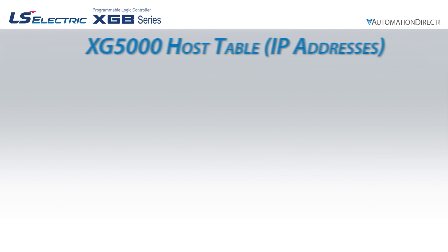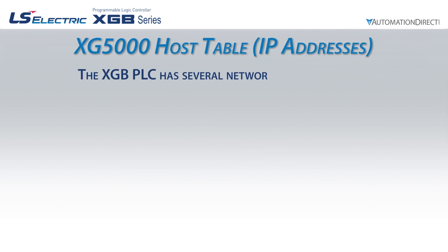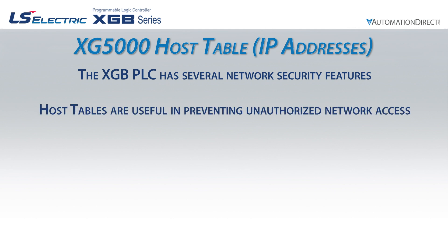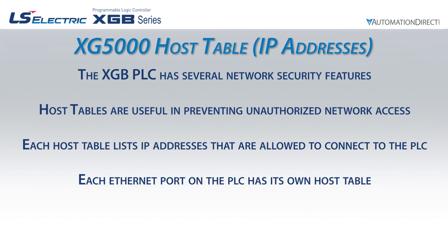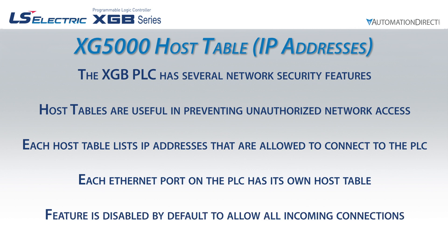In the modern age of remote access, network security is a very important aspect of industrial controls. The XGB PLC allows the user to set up host tables that prevent unauthorized remote communication access to the information in the PLC. These host tables are lists of IP addresses that are allowed to access the Ethernet ports. Each Ethernet port has its own host table. By default, these host tables are disabled to allow any incoming IP address. Let's enable the host table for the internal Ethernet interface on our CPU.